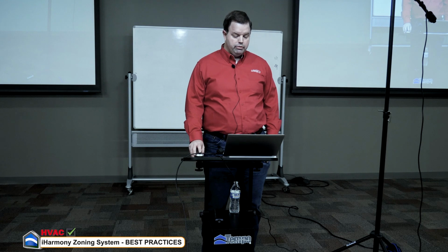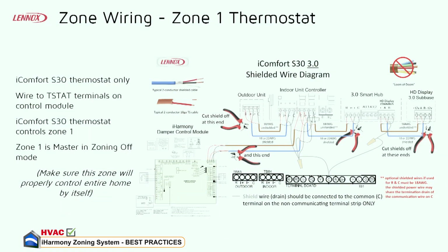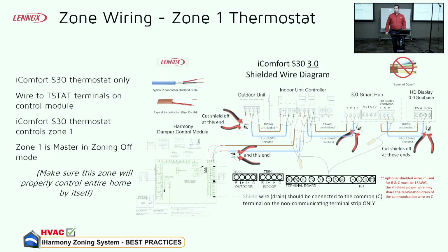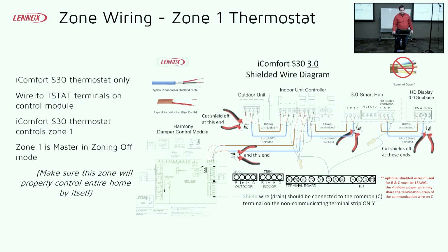I know a lot of times you may not get to make that call out on the job, but that can be a critical point, especially if you're experiencing troubles at startup. But you'll see it shows, in this case, taking the ground wire from a shielded cable back down to common, and you do that same thing with additional conductors if you're using multi-conductor. But like I say, if you can eliminate that, at least in the communication wiring from the zone board to the indoor unit and the hub to the indoor unit, that will do a lot, just running 2 conductor there.